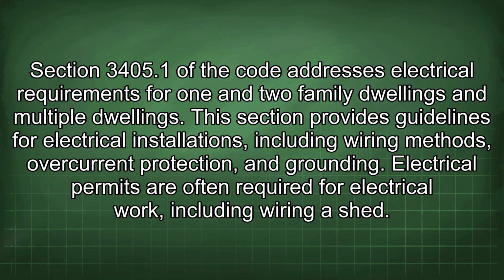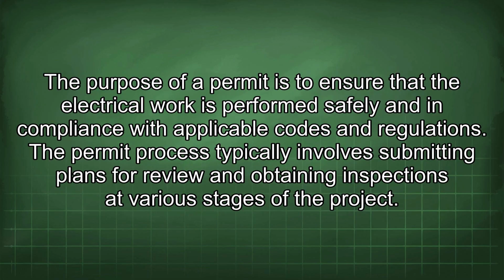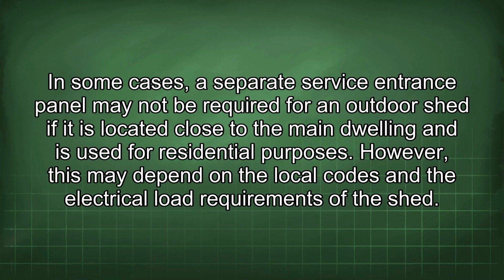This section provides guidelines for electrical installations, including wiring methods, overcurrent protection, and grounding. Electrical permits are often required for electrical work, including wiring a shed. The purpose of a permit is to ensure that the electrical work is performed safely and in compliance with applicable codes and regulations. The permit process typically involves submitting plans for review and obtaining inspections at various stages of the project. In some cases, a separate service entrance panel may not be required for an outdoor shed if it is located close to the main dwelling and is used for residential purposes. However, this may depend on the local codes and the electrical load requirements of the shed.